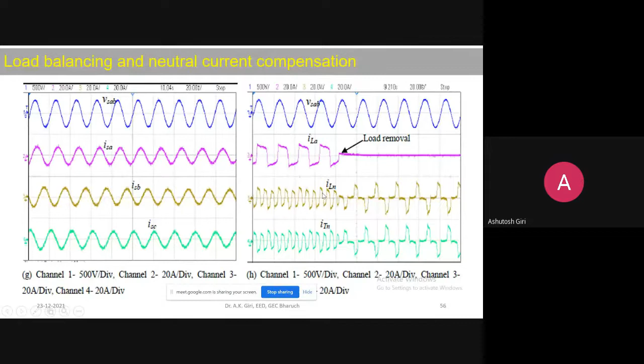These are some steady state results. We can see harmonics in the load current and in the supply current. Load current harmonics are almost 34 point something percent, but we get harmonics in the supply wave of less than 5%, as per IEEE standards.